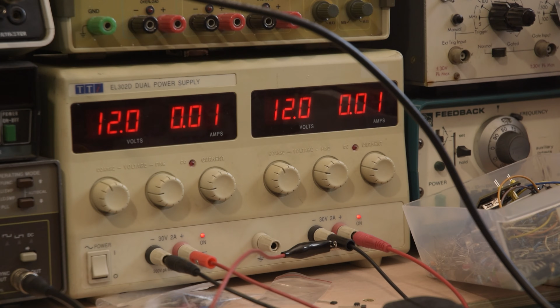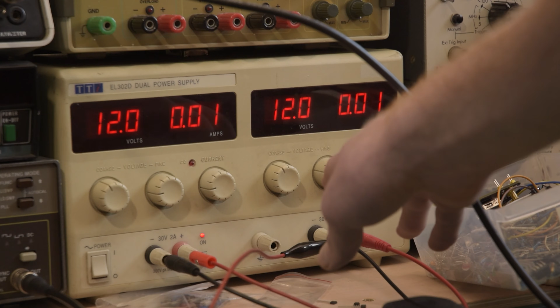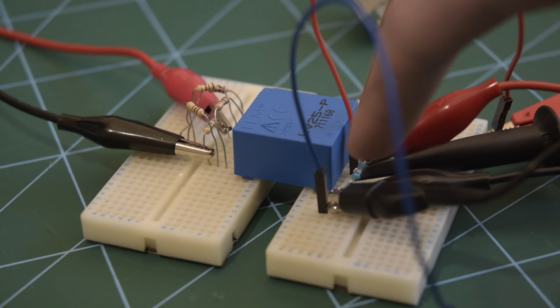You can see both outputs of my power supply are set to 12 volts, creating a bipolar supply: minus 12 volts on one side, plus 12 volts on the other. That feeds the secondary side of this transducer, while the primary side is fed by a current derived from the voltage we're trying to measure. The output has 3 pins: positive, negative, and an output that just carries the current used for the secondary winding of the internal magnetic stuff.